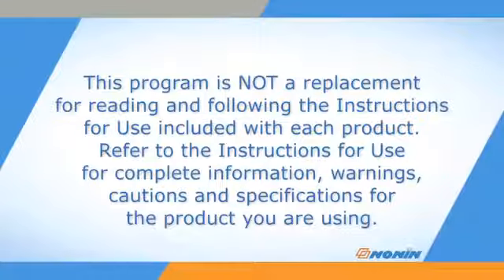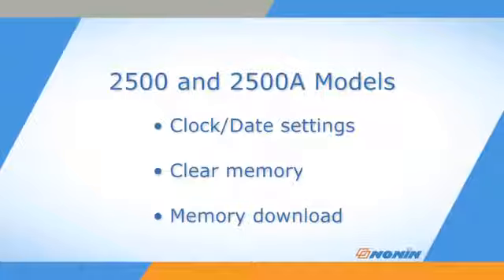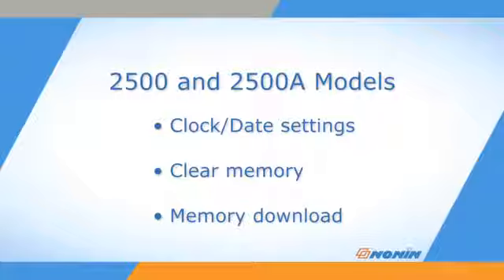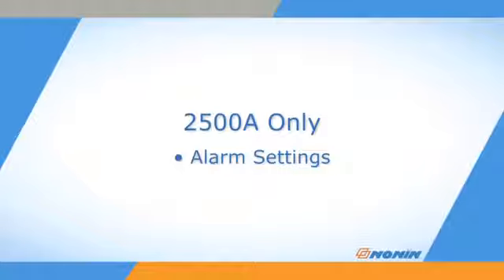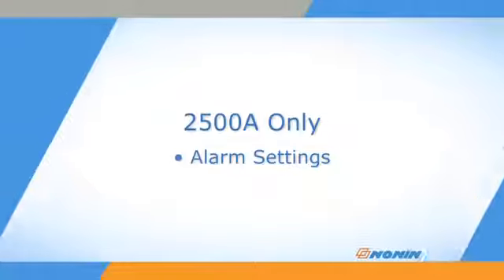On both the 2500 and 2500A models, setup mode is used to set or disable the clock and calendar, clear the oximeter's memory, and memory download. On the 2500A model only, setup is also used to adjust alarm settings.